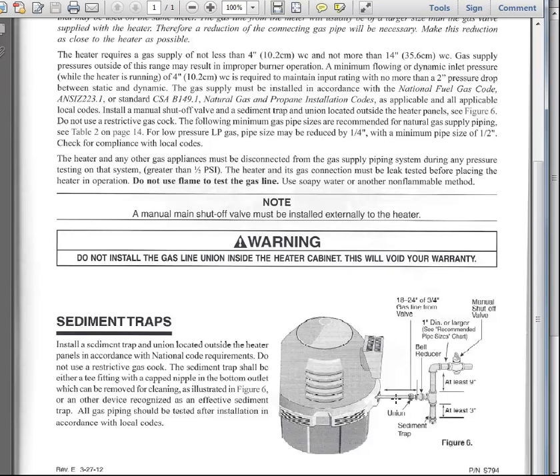What can happen outside the heater if the union loosens up and some gas does bubble out? Yeah, it's a big deal, but the probability of explosion is really slim. But if you put this union inside the gas cabinet and it starts leaking and surrounds that, and the fan motor turns on to start firing up your heater, it sucks all that propane in. You got a massive explosion.